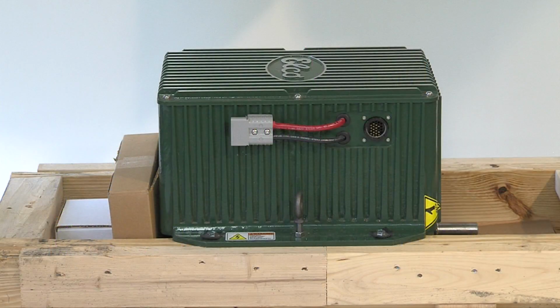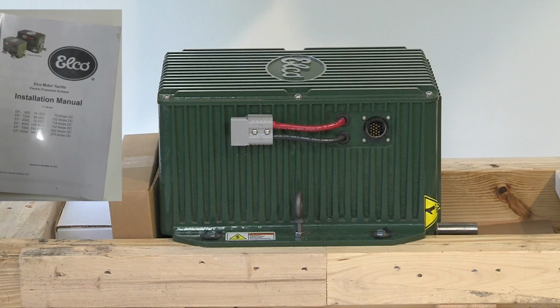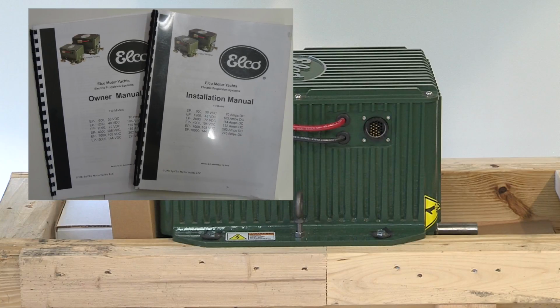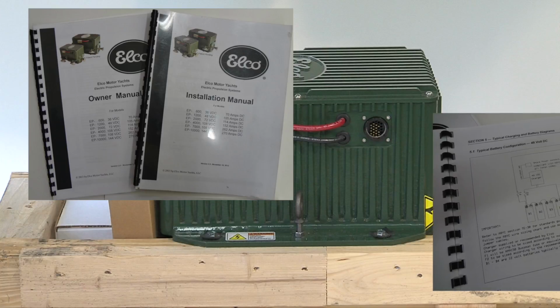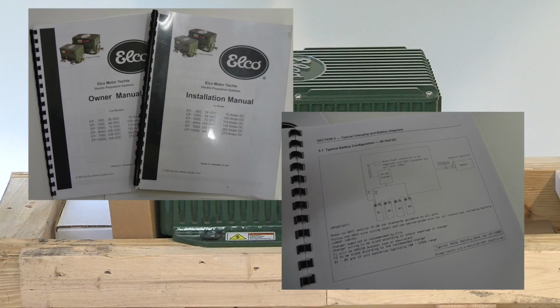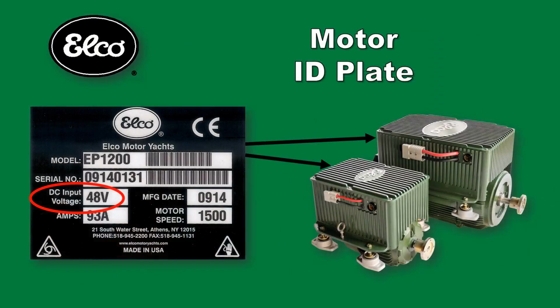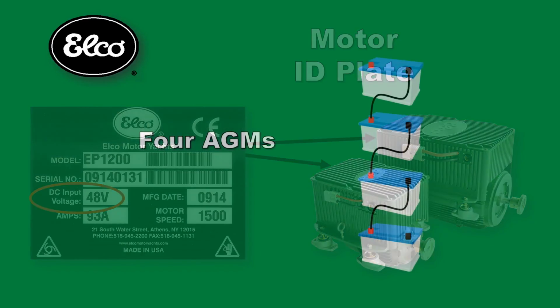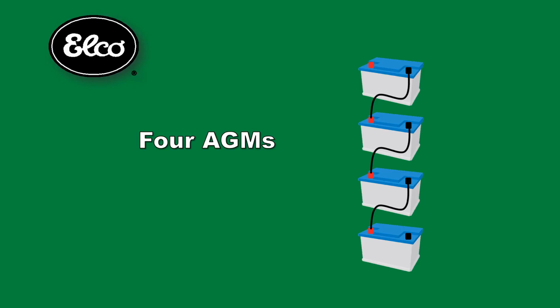When you purchase an Elco EP motor, installation and owner manuals are provided. The installation manual contains a wiring diagram which illustrates what we explain in this video. Confirm your motor voltage requirements by referring to the identification plate found on the motor casting. We are using an Elco EP1200, which requires 48 volts DC. There are 48-volt lithium battery packs available for this application, but we will use AGM batteries instead.